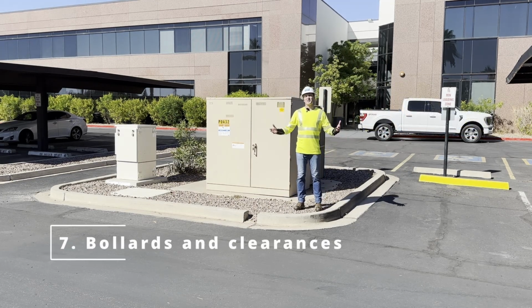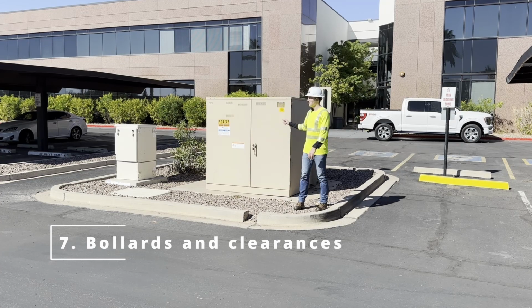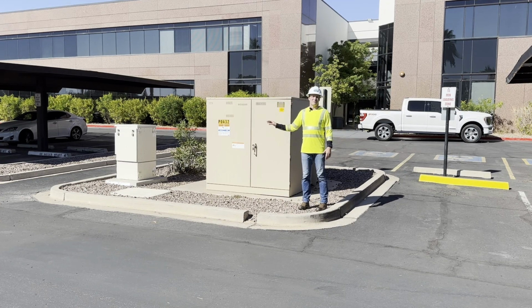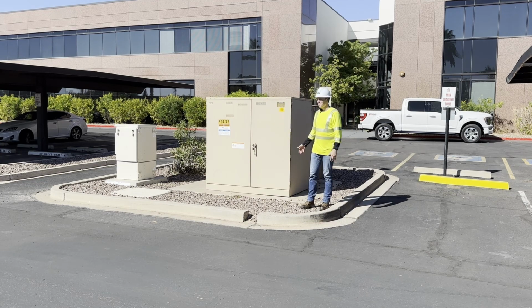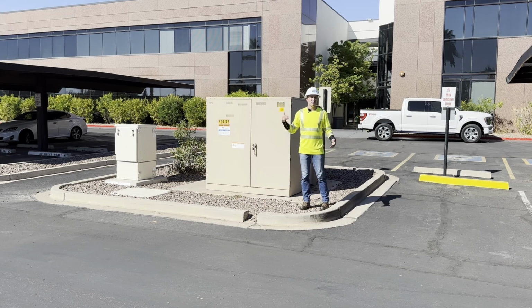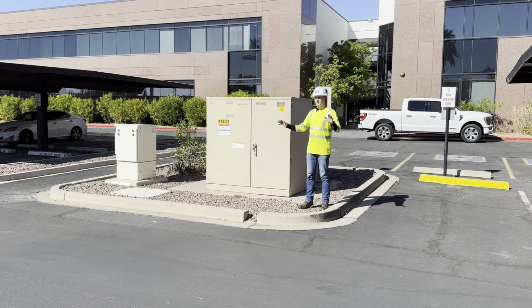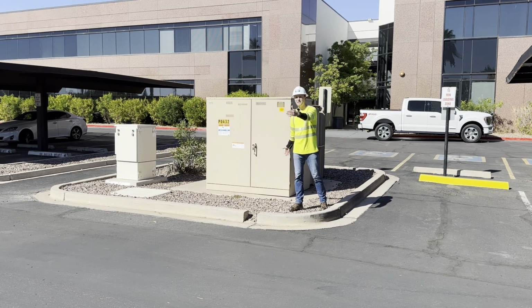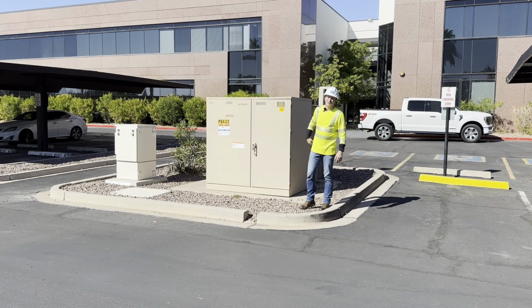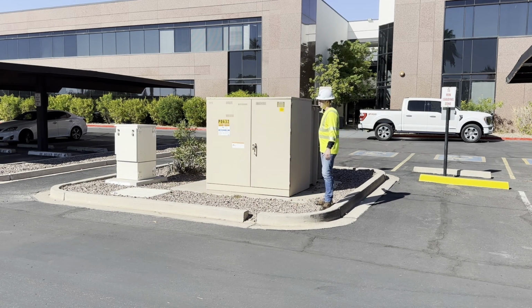Very important, number 7: bollards and clearances. As much as you'd love to put this wonderful piece of steel in the corner of your property, fenced off behind a bunch of bushes, you actually need to maintain certain clearances in the front, sides, and back of the transformer so your electric utility can safely maintain it on your behalf. Generally speaking, you need about 10 feet of clearance in the front, 3 feet on both left and right side, and about 3 feet in the back.